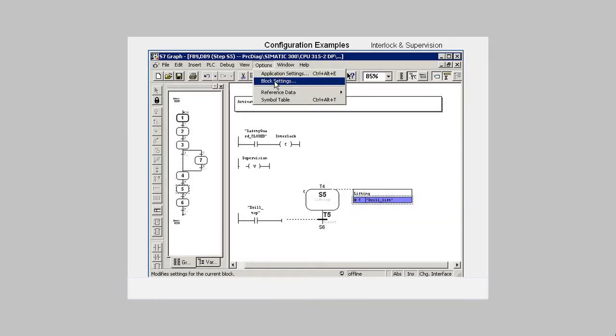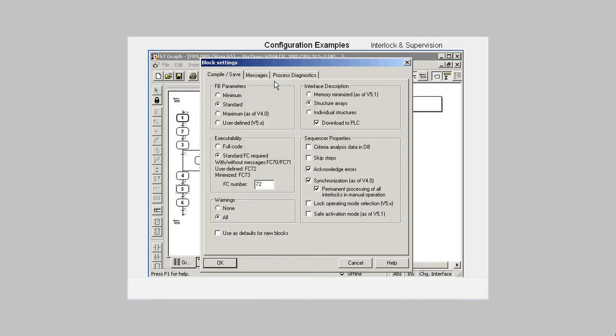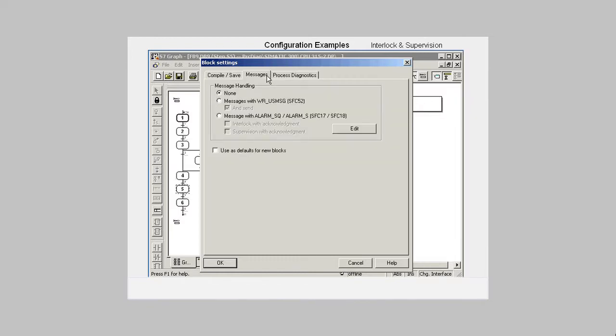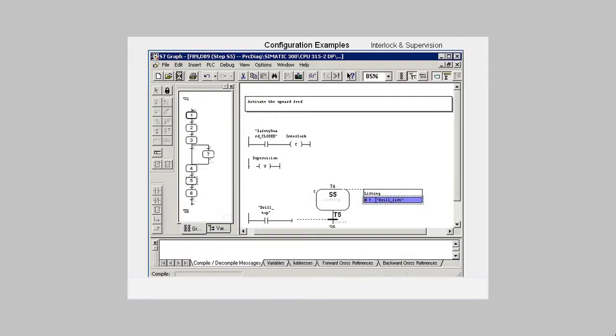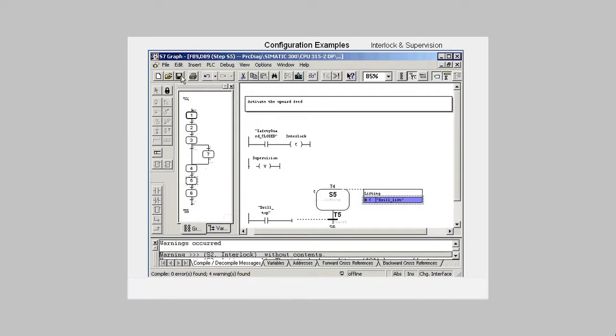We open the block settings dialog and in the messages tab we activate display acknowledgement on the HMI device, both for interlock and for supervision. We acknowledge the dialog and then save the sequencer. Load it into the CPU and close the editor.